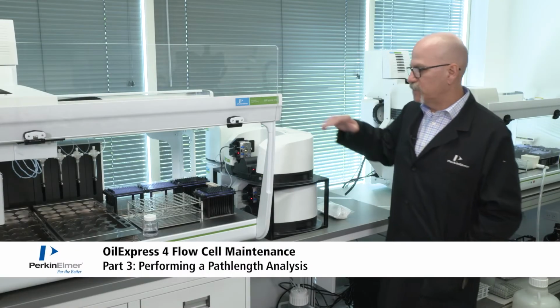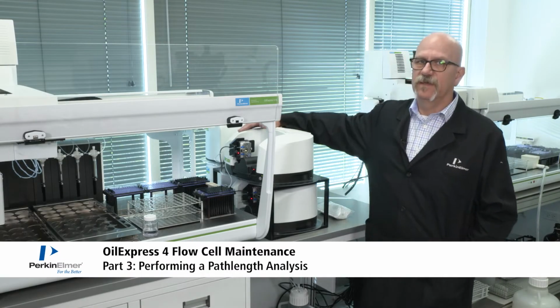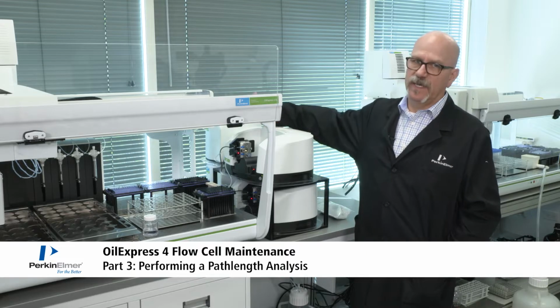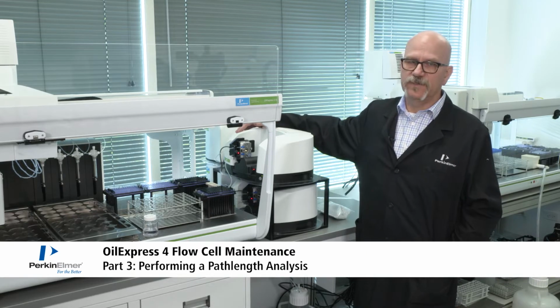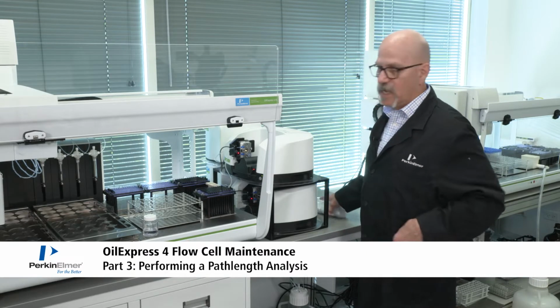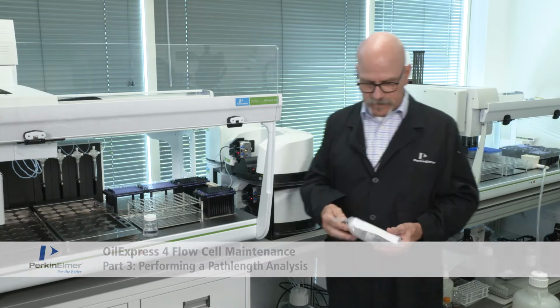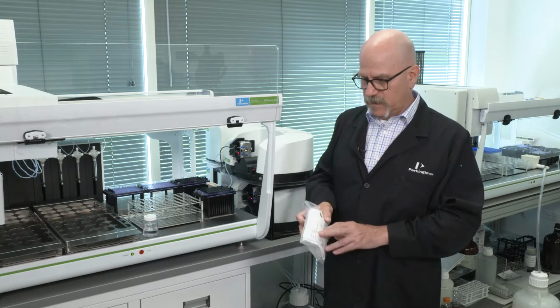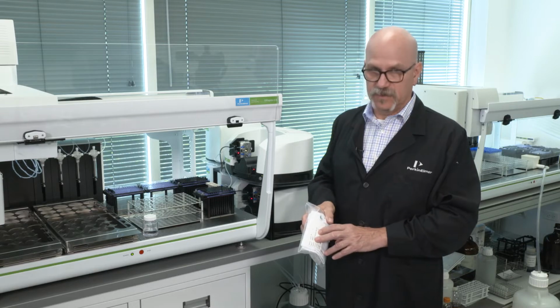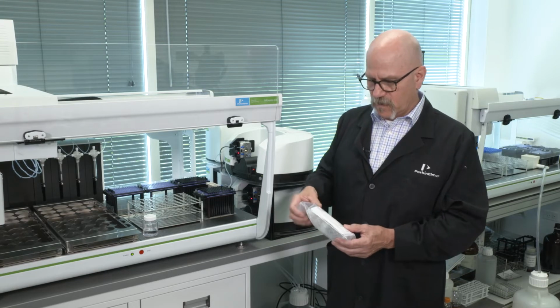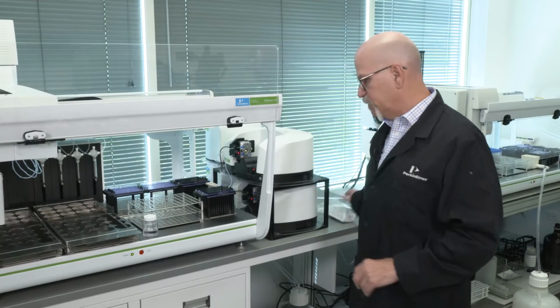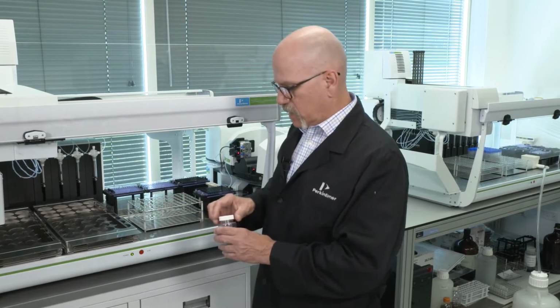Once we've finished cleaning our flow cell, reassembling everything, and we've collected the new empty cell reference spectrum, now it's time to do a Pathlength calibration. To do that, you're going to need the Pathlength calibration fluid that should have come with your Oil Express. Here we have some that's already been prepared and in a bottle.